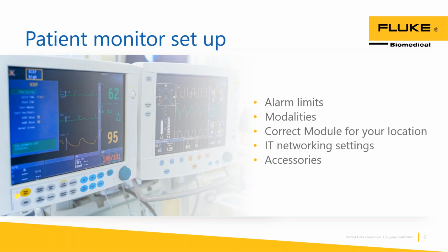So we're going to talk about this a little bit more down the line when you're doing your PM procedures, but is that part of your procedure? Are we going through and making sure that we have the right accessories on the floor for that monitor? And does it have the right modalities? If you have a small or an infant or pediatric patient put in to an ICU, is that monitor capable of having the parameters changed to that child? So there's some additional considerations that may be getting lost in here, especially as we get more and more devices that we're responsible for.